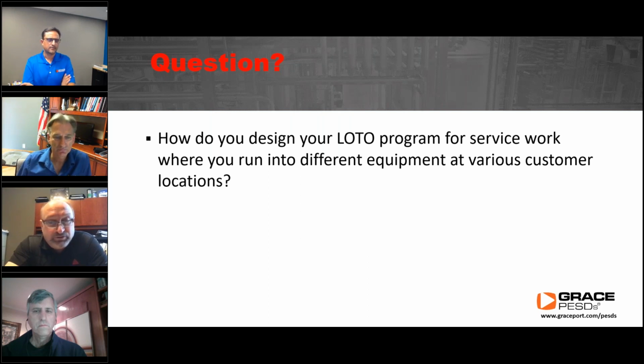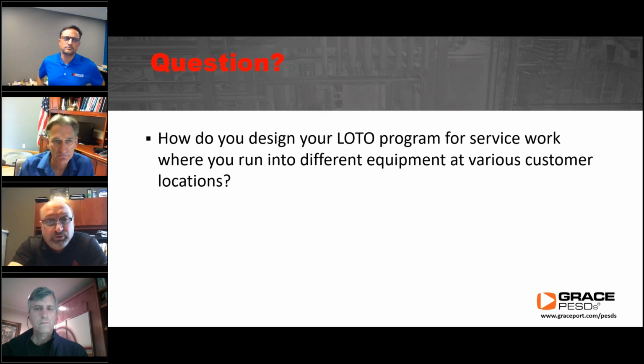So when I read that question, the answer I come up with is that your lockout tagout program, defined by your employer with additional information from Article 120 of 70E, is applied the same at every client site. You're not going to compromise your program's policy because a client requires you to do something differently. It's quite clear when establishing an electrically safe work condition that it's a generic 8-step process — you're not going to skip steps 2, 3, and 4 because that customer doesn't want you to do that. So again, generic lockout tagout programs and policy documents from your employer are applied the same at every client site. 70E provides specific content in Article 120, specifically around establishing an electrically safe work condition, and it's applied the same every time.